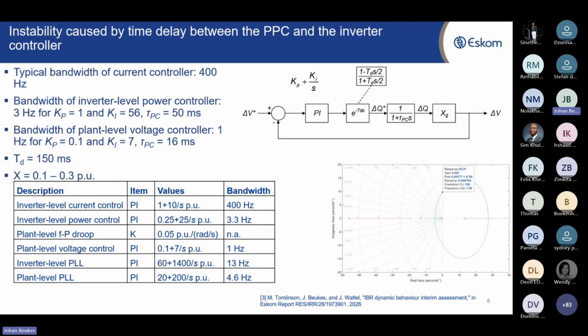This time delay is also applicable to grid forming inverters as soon as you have different levels of control in your system. That's why bandwidth on the different levels, and transport and communication delays, are very important when we specify these systems. Ideally, you want a single inverter connected to the grid, without the power plant controller, behaving as it should—as a voltage source—with a battery energy storage system.